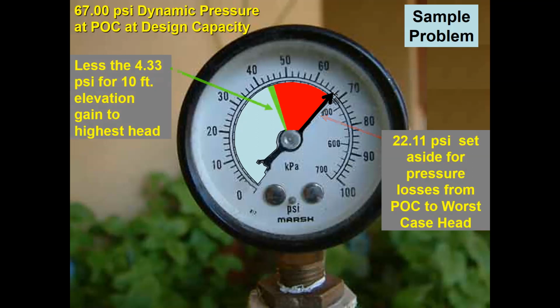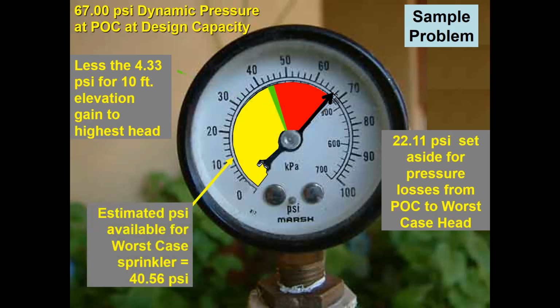Then we also had that elevation change, right? Because we're going 10 feet higher from our point of connection. So now we're down even further. We lost an additional 4.33 PSI. So now our estimated PSI for our worst case sprinkler is going to be 40.56 PSI. So that's how much pressure we can work with to operate that head.